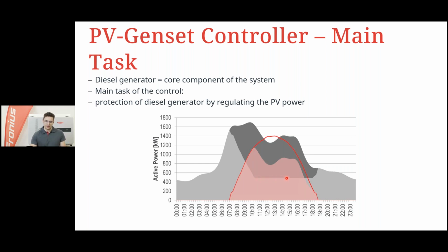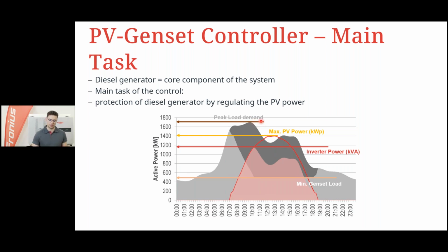And we also see a very straight line down below here, which would be a minimum genset load. We do not want the genset to run below that threshold, as it is a very poor efficiency, and we can prevent this by regulating down the output power of the inverter so that it does look like this. So we are following the load curve and reducing the output power to a certain limit so that the genset can run on its minimum genset loading. We also see here the inverter power that we use and also the maximum possible inverter power. But as we see in this setting, it does not work because of the minimum genset loading. And we also see the peak load demand at the very top here.